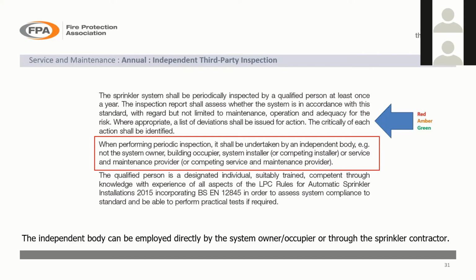If it's just one room, that's one thing. But if it's generic through the project, that they've all been overspaced, that would be raised as a red, because obviously your system wouldn't be fit for purpose there. If we found something like an ordinary hazard, one system had been installed into an ordinary hazard group 3 system, we'd raise that as a red, because obviously the system wouldn't have been designed and installed to meet the requirements of the classification which was appropriate. So red, amber and green is the way that we identify the criticality.